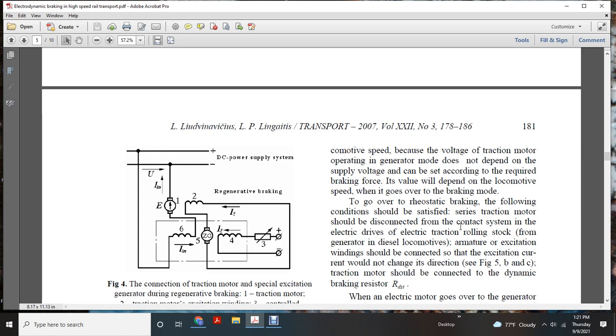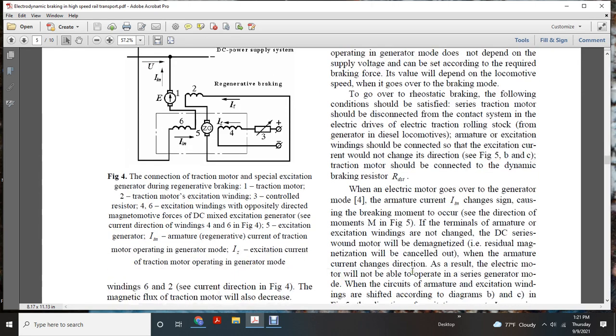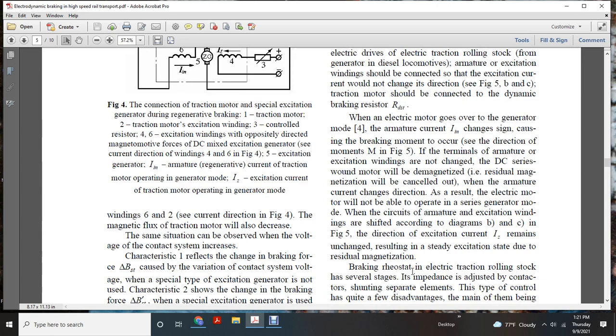In electric driven traction rolling stock, as with the generator of a diesel locomotive, the armature and excitation winding should be connected so that the excitation current does not change its direction. See Figure 5, B, and C. The traction motor should be connected with the dynamic braking resistor. The electric motor goes over to generator mode, with the armature current changing, causing the brake moment to occur in the direction of the moment. See moment M in Figure 5. If the terminals of the armature and exciting windings are not changed, the DC series wound motor will be demagnetized. Residual magnetism will be canceled out when the armature current changes direction.